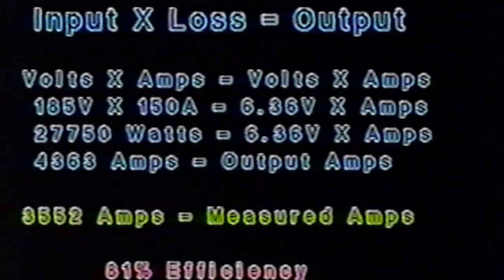My input voltage is 185, and my input amperage is 150 amperes coming out of the wall right here. I've got it on a 50 amp breaker - you have to hold it there about 5 seconds before you'll pop the breaker.